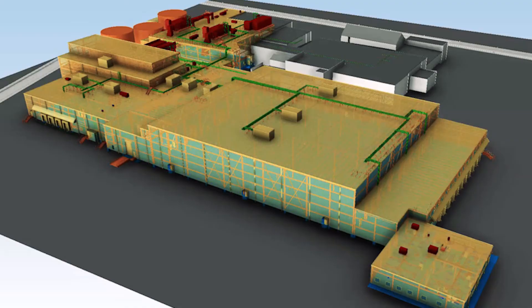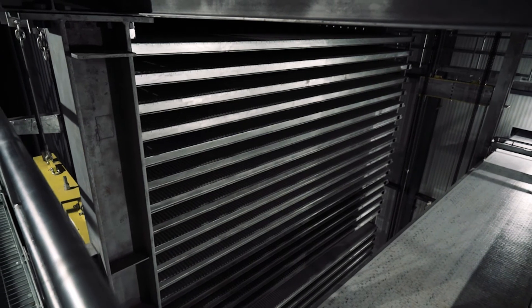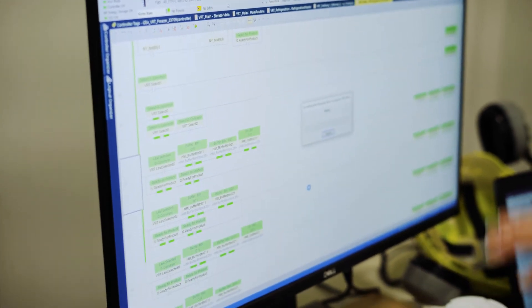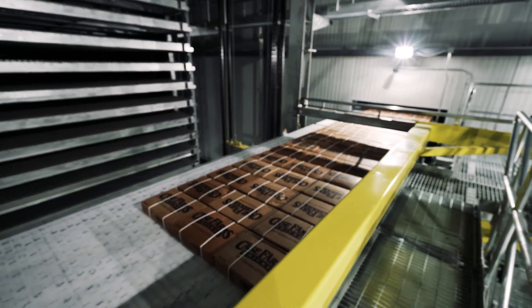Primus has a lot of experience with automated carton freezing solutions, also known as VRTs. The real advantage is that you're taking a carton and putting it into this big rectangular-shaped box — 50 feet wide, 50 feet high, 150 feet long. As that product goes in, it goes through in 17 hours or up to 24 hours, and at the other end it spits out hard as a rock. The VRT circulates air around the case, and because we're getting it from production within 15 to 20 minutes of the chicken being boxed, we're already putting it in the VRT.